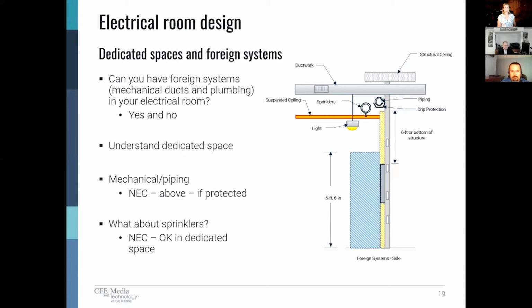It's not uncommon for the architects to want to lower the ceilings in the electrical rooms. So even though it says 6 foot or bottom of structure, what if the architect locates the bottom of structure 12 inches above your gear? Is that a violation of code, or is that more just poor practice because you've got to get your conduits out of the gear and be able to do both the install and future work? So it really is more of an issue of good practice. Next slide.